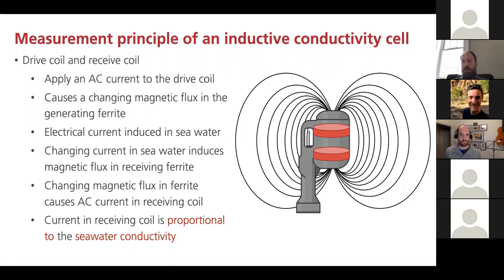In seawater, of course, the seawater conductivity changes according to different conditions. And the current that is passing through that seawater is seen in reverse, if you like, by that receiving ferrite. It induces a flux, and that flux induces a current in the receiving coil. And so that current in the receiving coil is linearly proportional to the seawater conductivity.